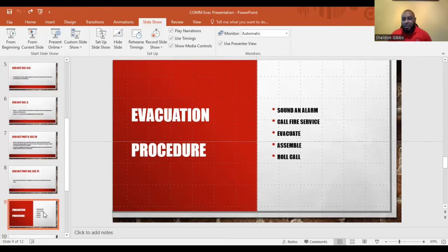Okay? So we evacuate. And where do we evacuate to? We evacuate to our assembly point or muster point. This point is an area that was identified based on our assessment again as an area safe or comparatively safe from the building. It must be an area directly away from the building. So in the event of any form of collapse, it must not collapse onto the muster point. In a fire situation, the heat, the smoke, the flames must not affect persons at the muster point. If there is a release of a gas, the wind must not blow the gases to the muster point.